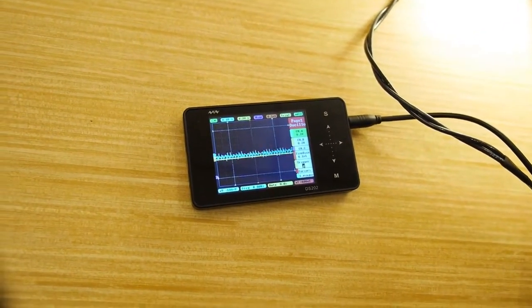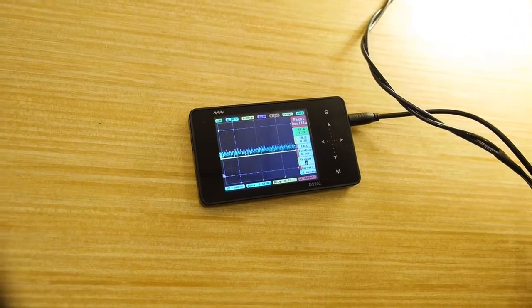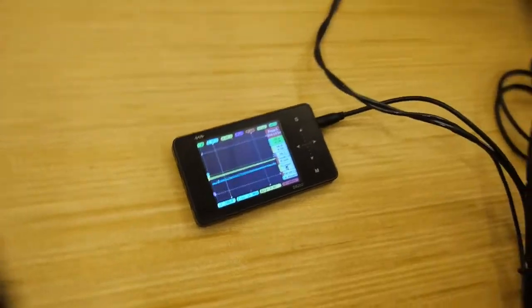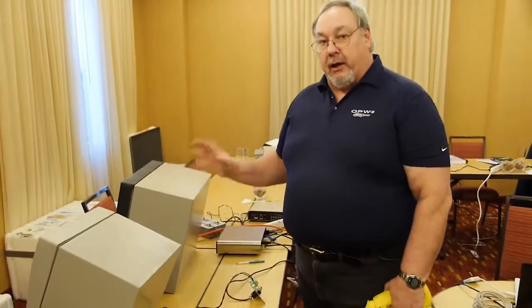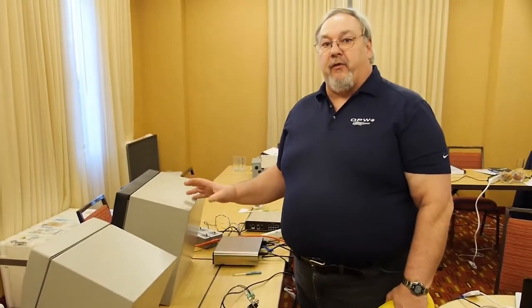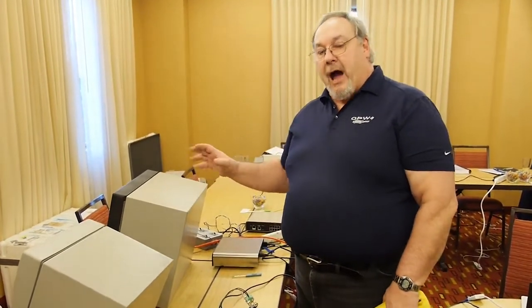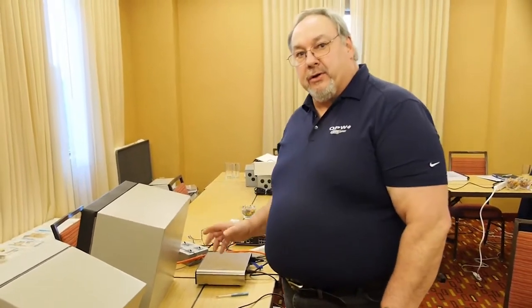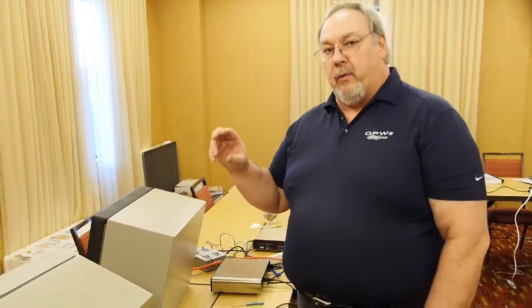One of the things we're recommending is the ability to isolate the systems. Take a look at the system if you're having issues, isolate it from the junction box first, trace it down and isolate it in places to see where you're getting noise. See if your wire connectors aren't done or if the wires aren't grounded properly or if wires are being run in troughs with high powered wire or in conduit with other wire that's not recommended by the manufacturer. This is just a tool to help troubleshoot any communication issues you may be having at site.